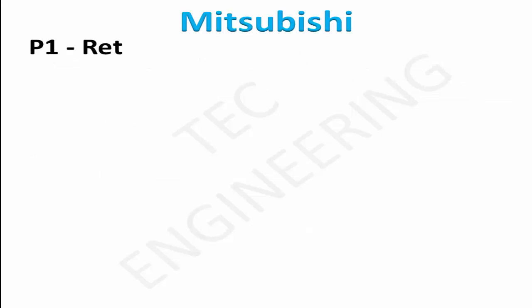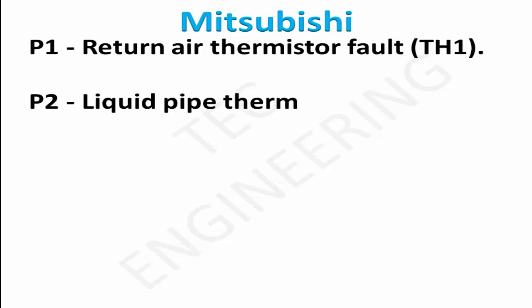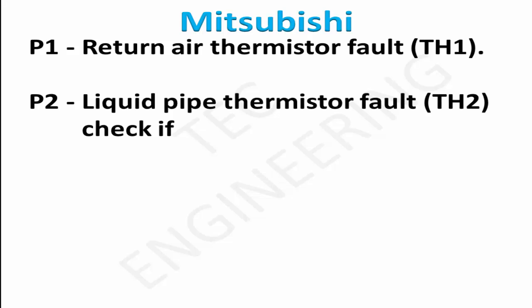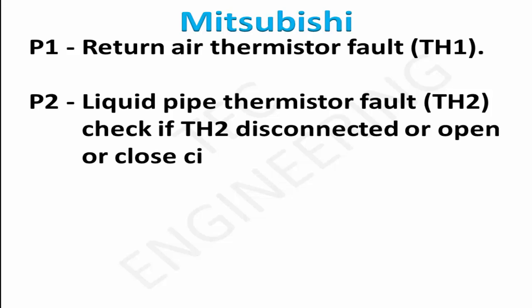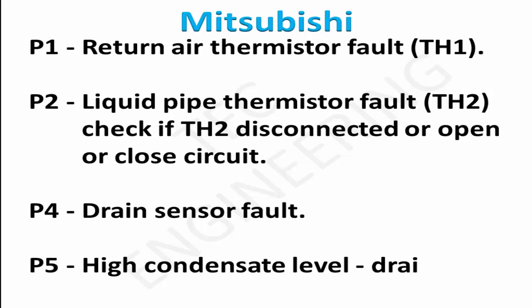P1: return air thermistor TH1 fault. P2: liquid pipe thermistor TH2 — check if TH2 is disconnected, open, or short circuit. P4: drain sensor fault. P5: high condensate level or drain pump failure.